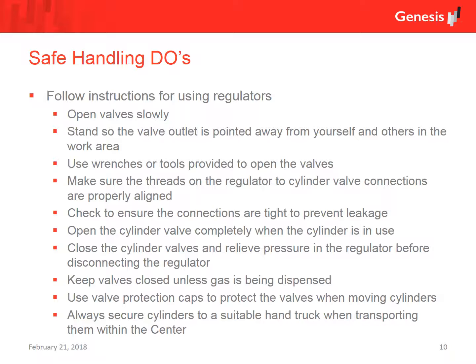That's especially with your helium. Keep valves closed unless gas is being dispensed. Use valve protection caps to protect the valves when moving cylinders. Always secure cylinders to a suitable hand truck when transporting them within the center. For your E-tanks, that is not necessary. You can handle those with your hands as they're much smaller than an H-tank. These primary rules apply to your H-tanks, which are much larger than our E-tanks.